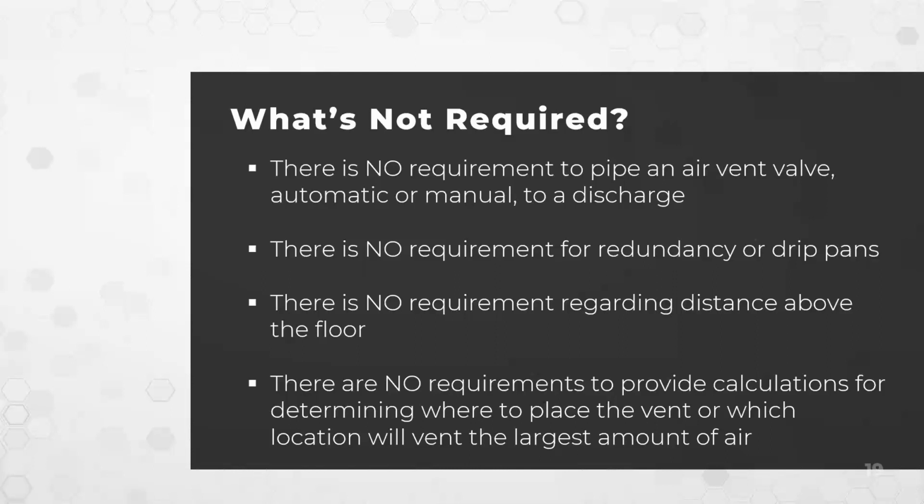As I said, most installs are air vents that have strainers on them, and those strainers have to be accessible. So you want to be very careful that you don't locate the air vent where it can never be reached. The highest point in the building may be a difficult location.